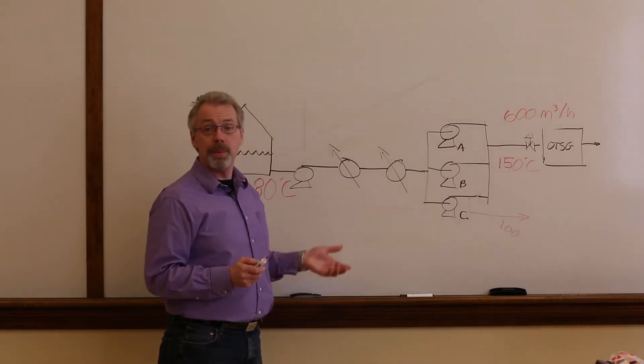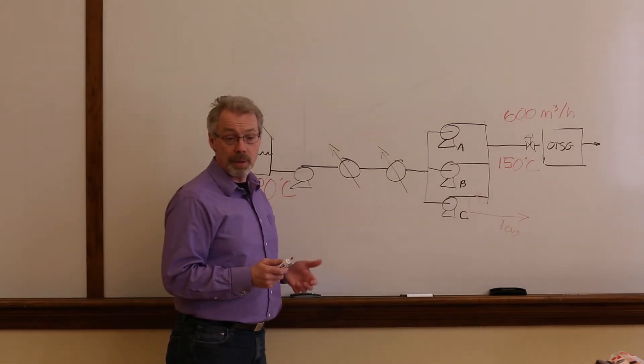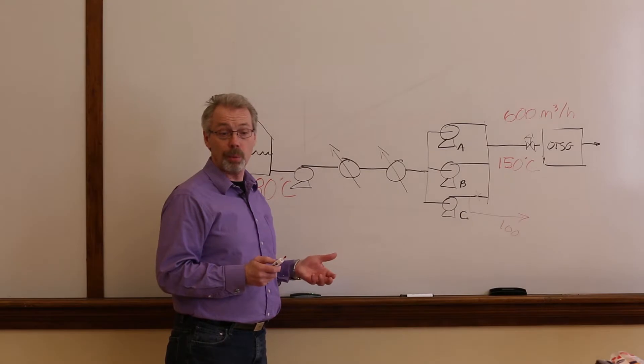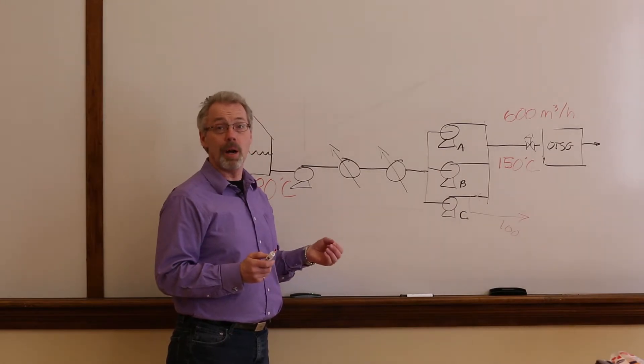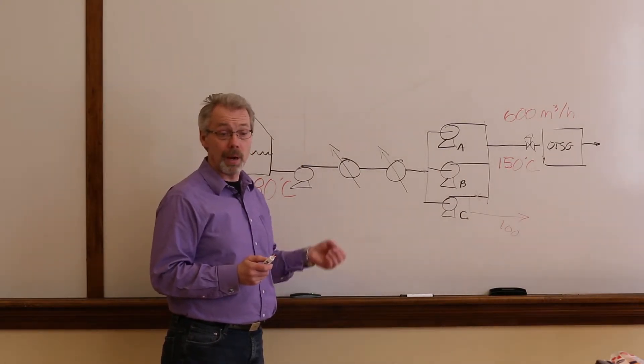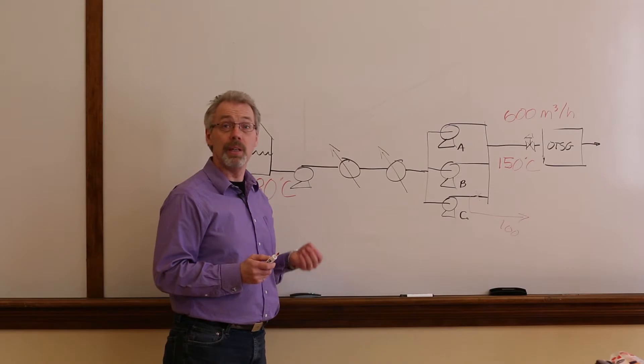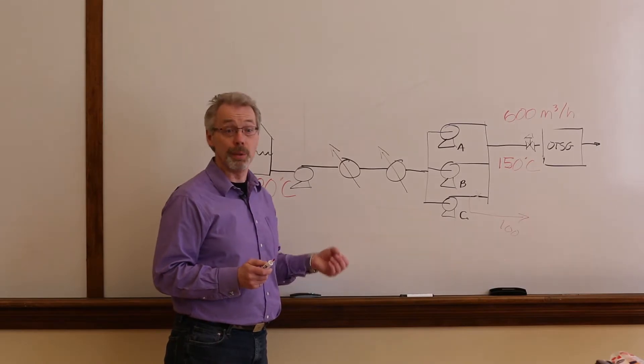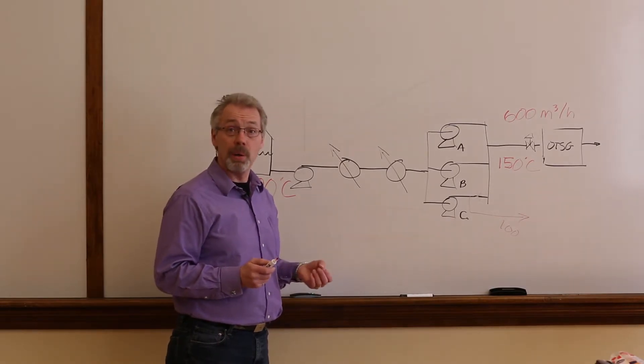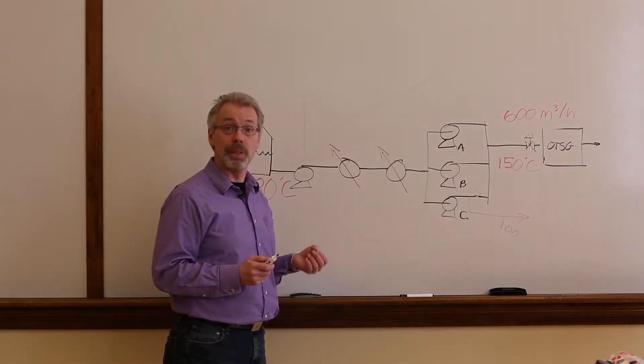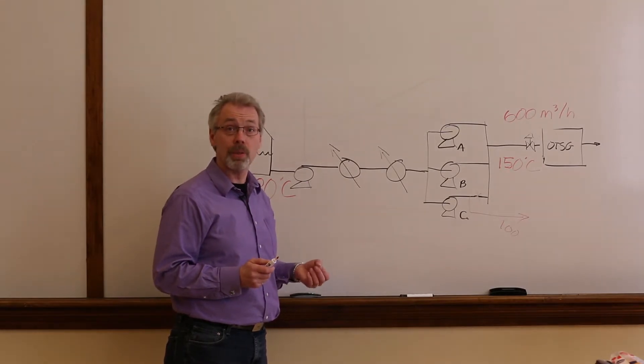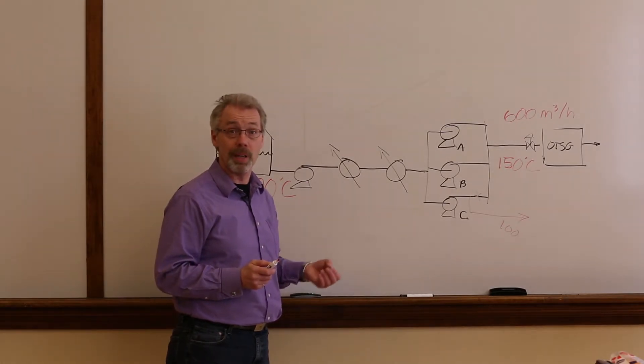When pump B is shut down, there is no more water being wasted, and the total flow rate immediately drops to 600 cubic metres an hour, and the temperature rise is now 70 degrees. This is how the pump swap procedure can result in a sudden increase and decrease in boiler feed water temperature.